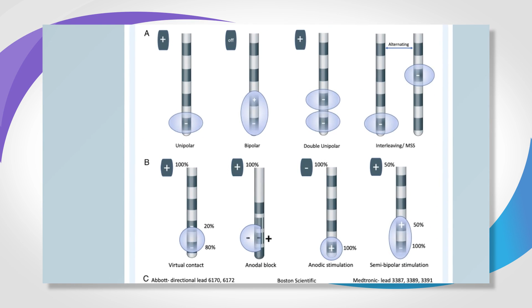Here I'm just trying to get closer to this picture so I can really show you. In section A, you see this negative contact on the electrode. The bottom contact is negative, and this little positive sign is meant to represent the case, or the battery, in the patient's chest. When you change a contact to negative, you make that contact the cathode, and the negative contact is the active one. It's where you're sending stimulation from, and the anode, the positive, is on the battery itself.